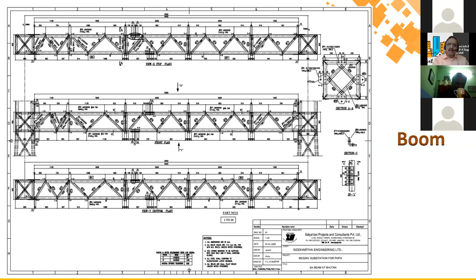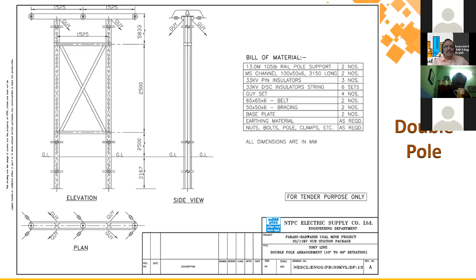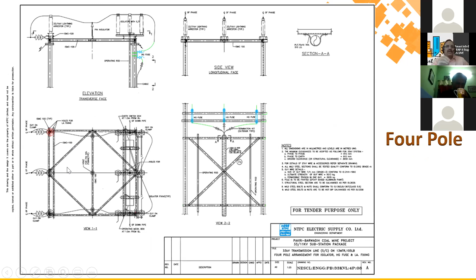So this is a double pole structure which you will see in most of these colonies for transformers, and these are like small substations. You take the incoming power, step down, and again supply back through the distribution line. This is a 2-pole structure; 4-pole structures are common, this one. And this is a 4-pole structure, as I explained. So you will have all the insulators, circuit breakers and all in the 4-pole structure. Suppose you have 33 kV to 11 kV, this 4-pole structure is enough for the substation. So these are all, and this is a transformer structure.